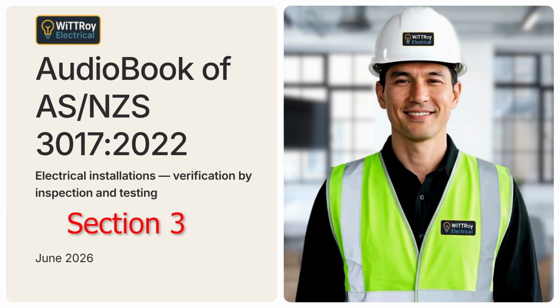For earthing, the MEN connection must be checked where the installation uses an MEN or TNCS system. The earth electrode must be checked. Earthing conductors must be checked, including size and identification. Equipotential bonding conductors must be checked, including size and identification. Connections, joints, and terminations must be checked. Protection against external influences must be checked. Connections to earthing arrangements for other systems must also be checked where applicable.